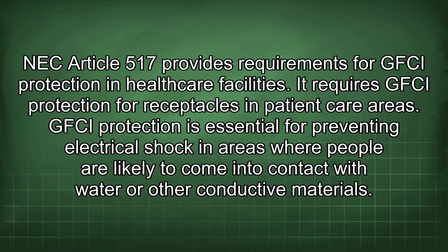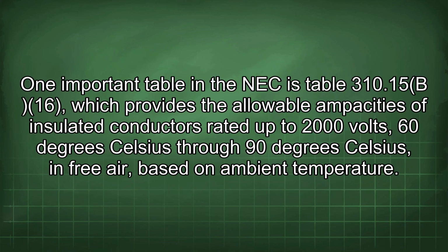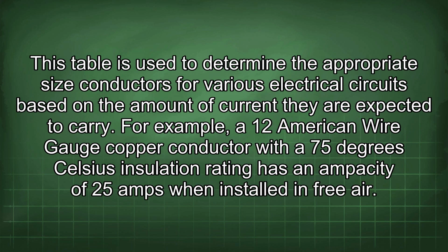or other conductive materials. One important table in the NEC is Table 310.15(B)(16), which provides the allowable ampacities of insulated conductors rated up to 2000 volts, 60 degrees Celsius through 90 degrees Celsius, in free air, based on ambient temperature. This table is used to determine the appropriate size conductors for various electrical circuits based on the amount of current they are expected to carry.